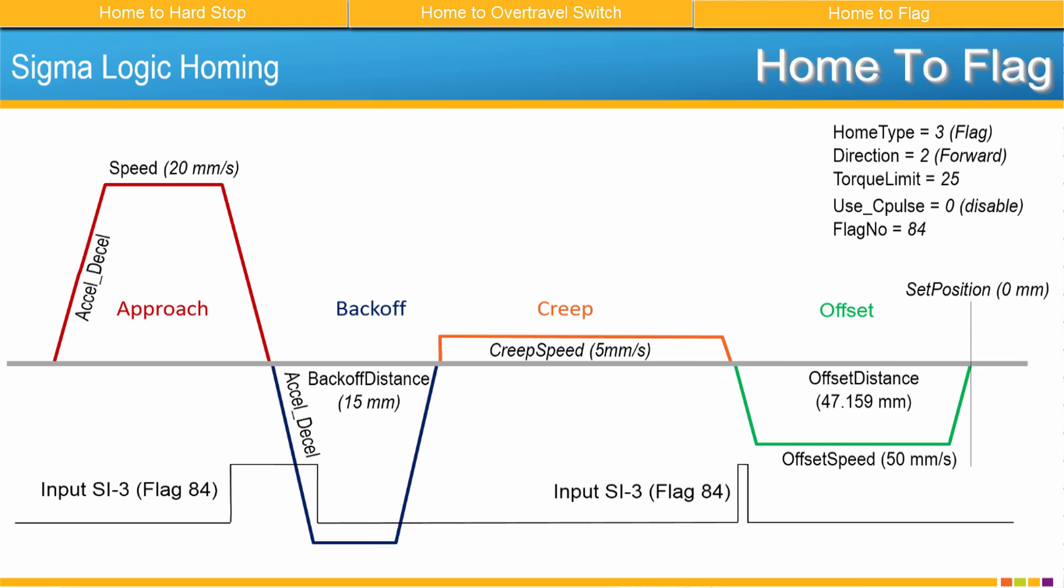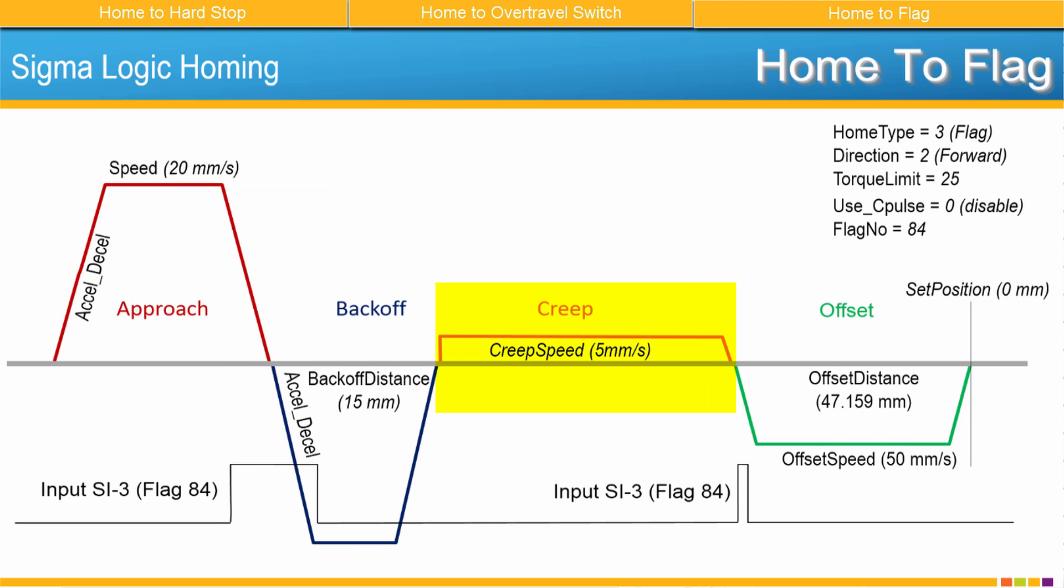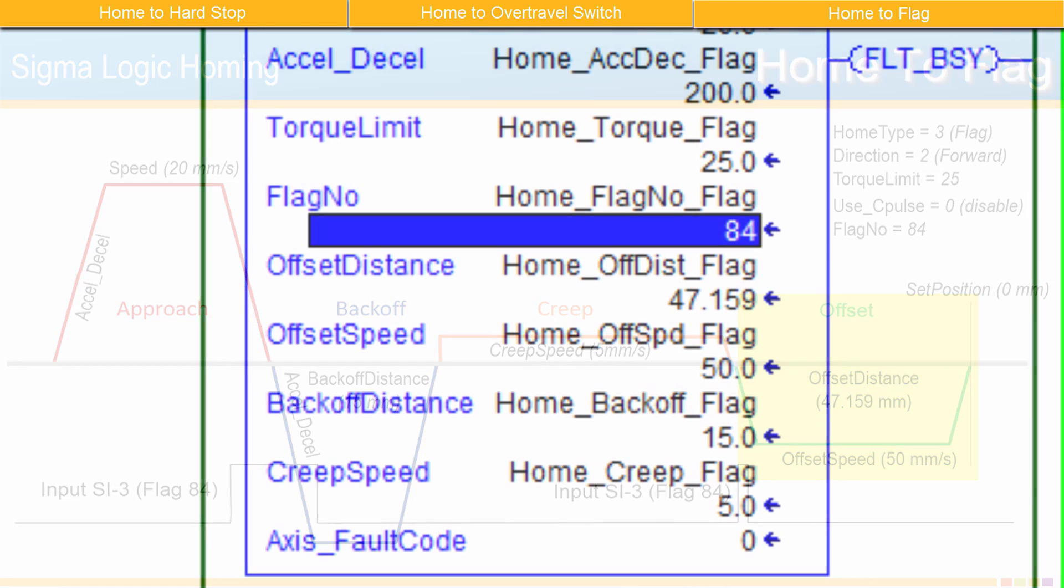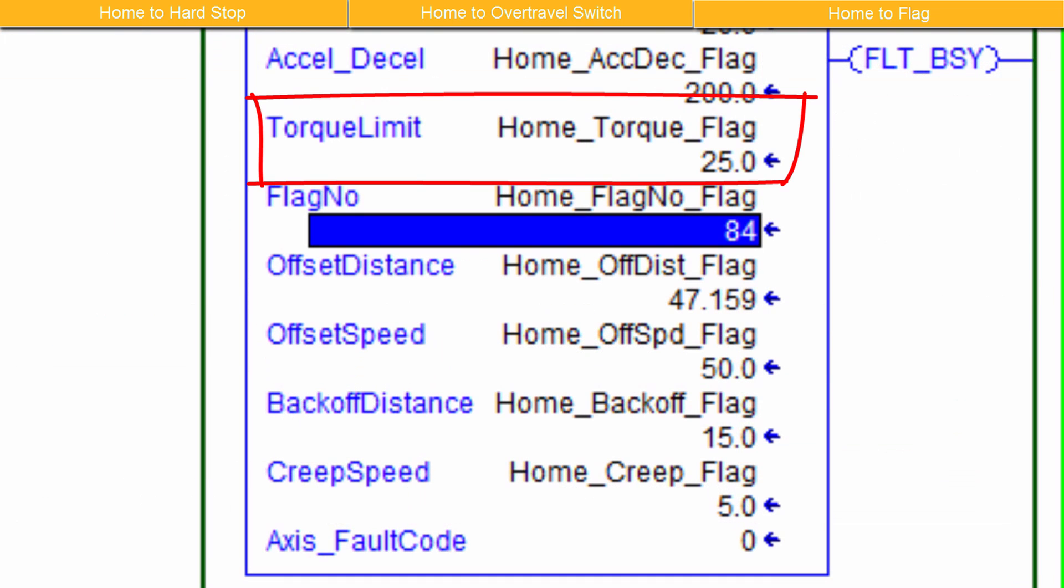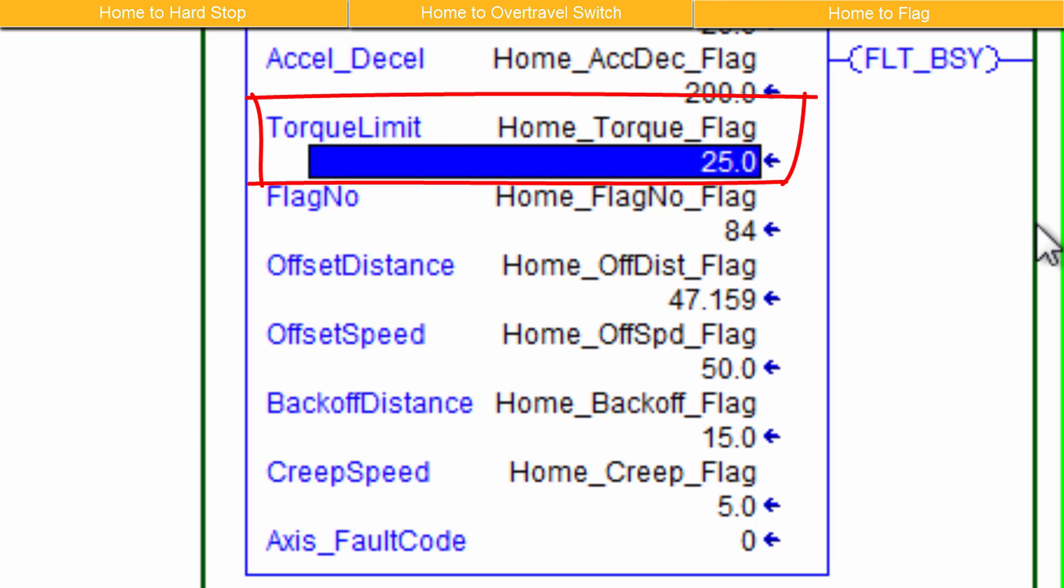The move sequence for home to flag is similar to home to over travel consisting of the same four moves: Approach, Back Off, Creep and Offset. And again, a torque limit applies to the entire homing sequence and must be set to 5 or higher. I'll use 25% which means if the torque exceeds 25% during homing, motion will stop.